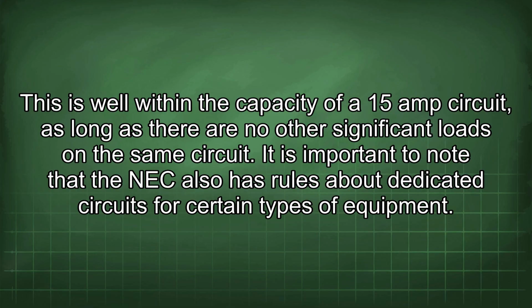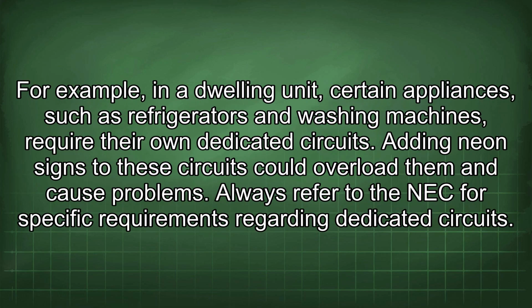on the same circuit. It is important to note that the NEC also has rules about dedicated circuits for certain types of equipment. For example, in a dwelling unit, certain appliances, such as refrigerators and washing machines, require their own dedicated circuits. Adding neon signs to these circuits could overload them and cause problems. Always refer to the NEC for specific requirements regarding dedicated circuits.